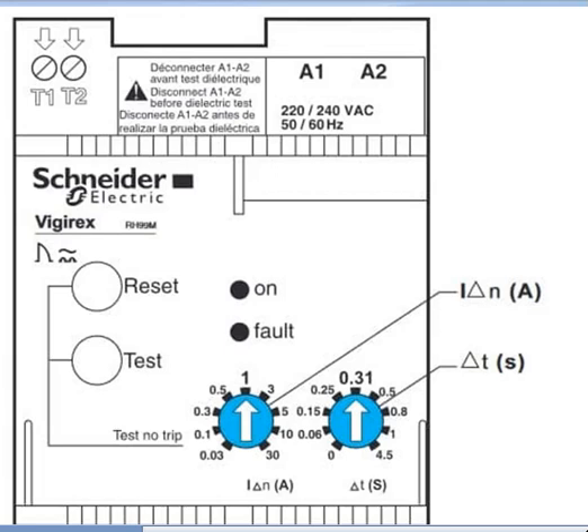I'm going to discuss with you about earth leakage relay. So friends, earth leakage relay is a type of protection relay that gives protection against earth leakage. If there is any earth leakage in the circuit, it is going to trip your main breaker, and it will be connected in the control side.